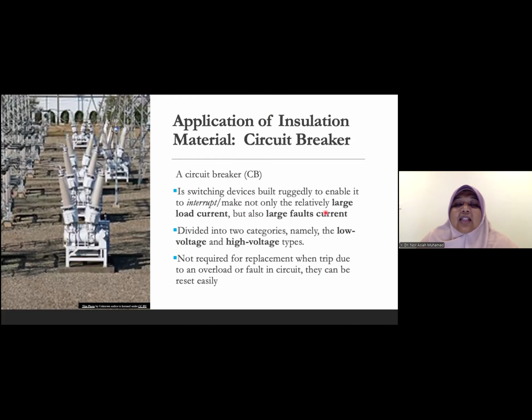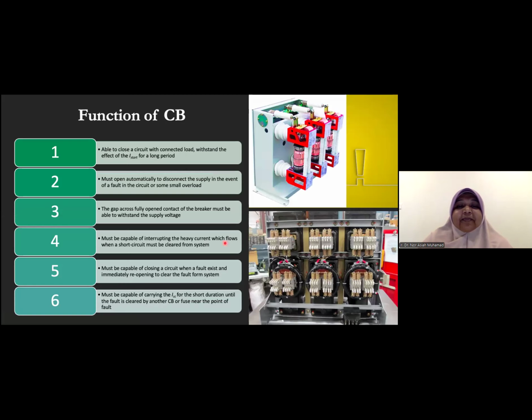So at high load current, but also at very high, large fault current. So it's divided into two, which is low voltage circuit breaker and also high voltage circuit breaker type. So circuit breaker, once it is on or off, we are... so if a fuse is burned, you need to replace it. But in high voltage application, once the circuit breaker has interrupted, you can re-energize it.